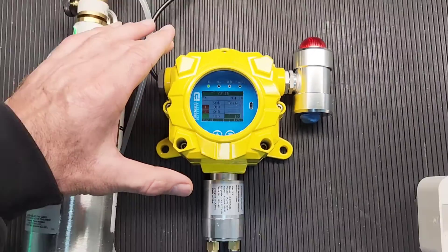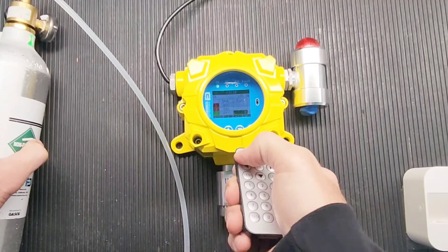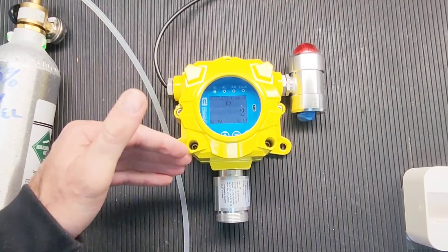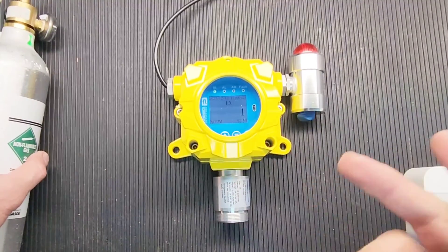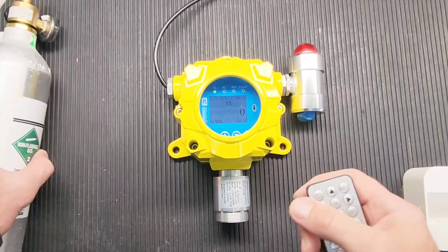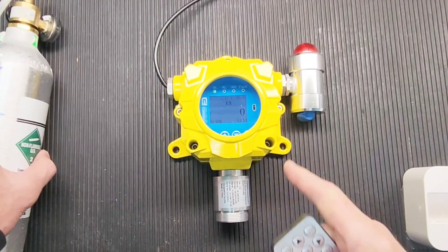That's a nicely calibrated unit ready for fresh operation. Once done, turn off the gas, take the tube off, take the cap off, and go back to the menu. Allow time for the reading to come down to zero depending on the concentration used. If it flutters around 1 or 2, you may have a noisy environment — keep zeroing until you get a stable zero. This unit is ready to rock and roll. Be well, be safe, and see you soon.